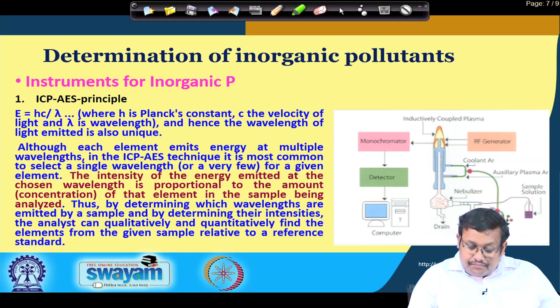Now, the wavelengths used in atomic emission spectrometry or ICP-AES range from the upper part of the vacuum ultraviolet, that is 160 nanometer, to the limit of visible light, which is around 800 nanometer in the total electromagnetic spectrum. Now, as borosilicate glass absorbs light below 310 nanometer and oxygen in air absorbs light below 200 nanometer, optical lenses and prisms are generally fabricated from quartz and optical parts are evacuated or filled by a non-absorbing gas such as argon, because if there is a presence of oxygen, there will be absorption of light. So, that is why they are either evacuated or filled by a non-absorbing gas like argon.